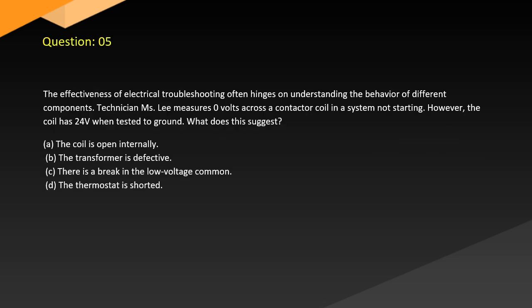Question 5. The effectiveness of electrical troubleshooting often hinges on understanding the behavior of different components. Technician Ms. Lee measures 0 volts across a contactor coil in a system not starting. However, the coil has 24 volts when tested to ground. What does this suggest? A. The coil is open internally. B. The transformer is defective. C. There is a break in the low voltage common. D. The thermostat is shorted.